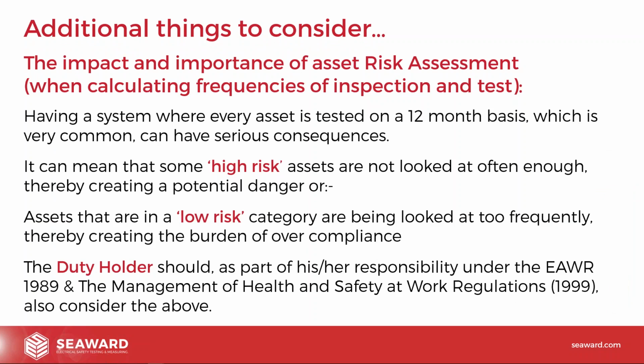So, additional things to consider, obviously the importance of risk assessment from this side of things. Having a system where every asset's tested every 12 months is very common and can have serious consequences. As we said, it can mean that some high risk assets are not looked at often enough, thereby creating a potential danger. Assets that are low risk category may be looked at too frequently. And it's really down to the duty holder to actually make this decision.